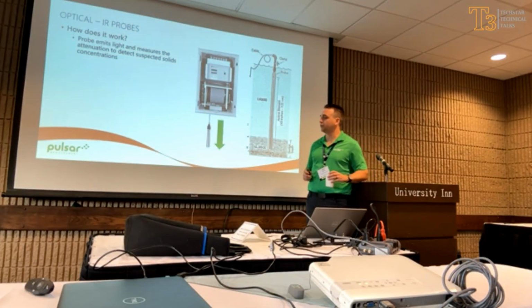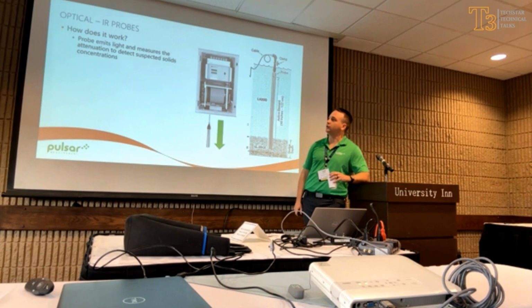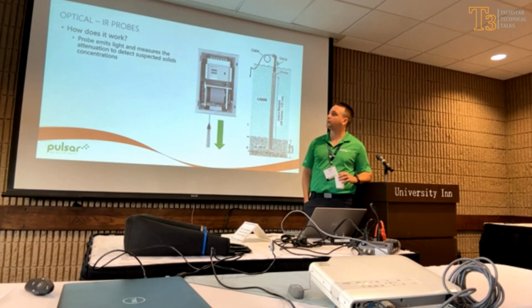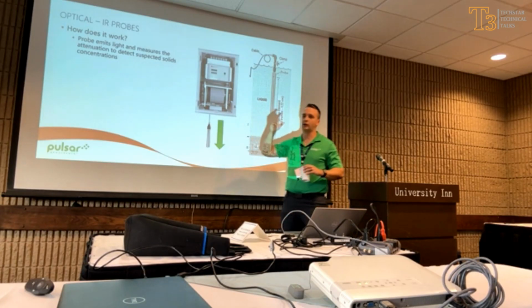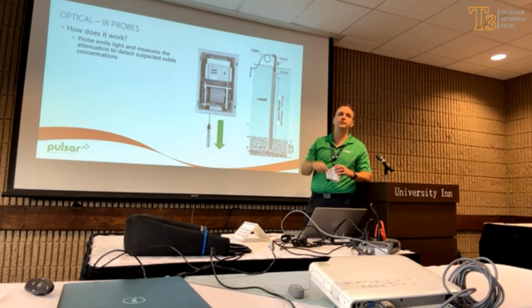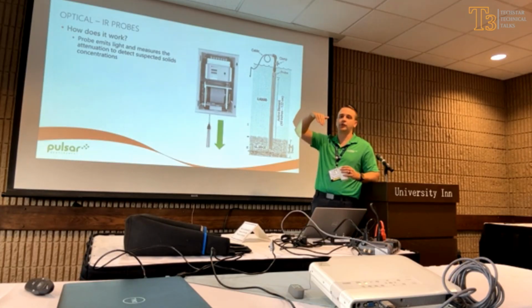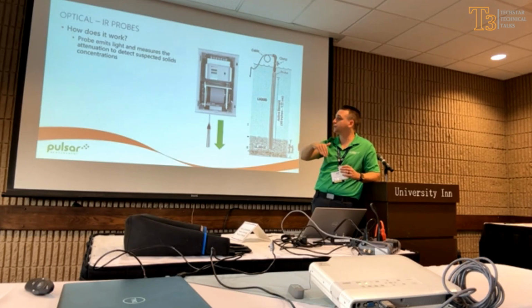Similar to the last one, but this one is fully automated. Some manufacturers make an optical or infrared probe on a spool piece. The system will automatically, every so often, let that probe down into the blanket, and as time goes on, stop at different points, taking a measurement at the clear supernatant, at the settlement layer, at the floc, and then at the actual blanket, giving you a nice automatic profile.